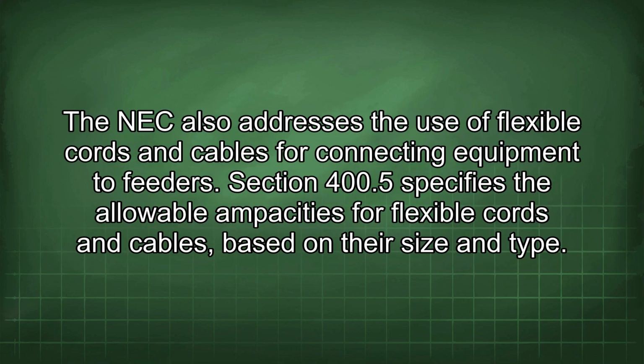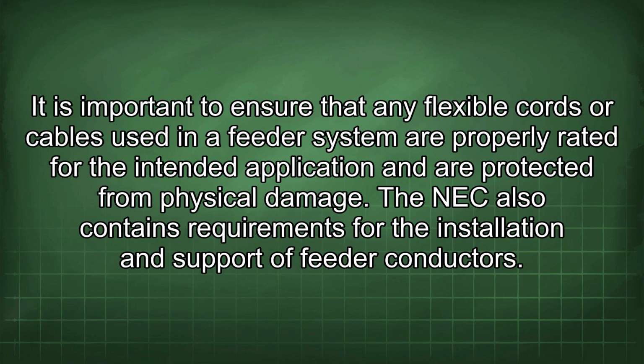The NEC also addresses the use of flexible cords and cables for connecting equipment to feeders. Section 400.5 specifies the allowable ampacities for flexible cords and cables based on their size and type. It is important to ensure that any flexible cords or cables used in a feeder system are properly rated for the intended application and are protected from physical damage.